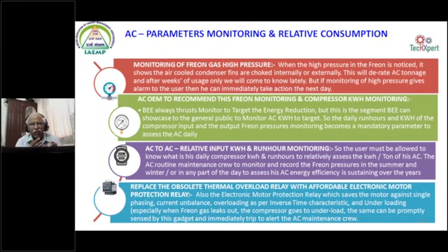In any of the air conditioners, the incoming kWh for the compressor and the run-hour for the given compressor can start from a 1-ton split, and it can go to a 100-ton package also. On the higher sizes, the OEMs have definitely given it, but it has to come to the split also. See, you are using it in a bank or in an office, multiple air conditioners, you can show the relative efficiency of the air conditioners with respect to the kWh and the run-hour consumption. So the relative input and run-hour monitoring, and the output freon gas pressure, whether higher gas pressure or lower pressure, will show whether the system is healthy.